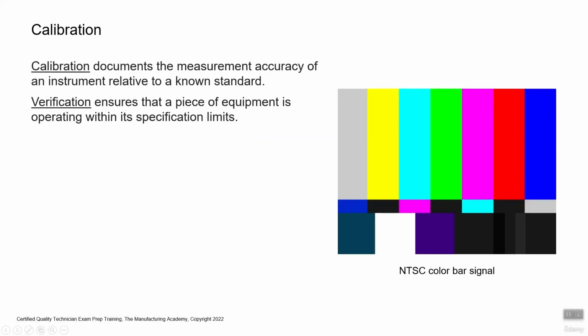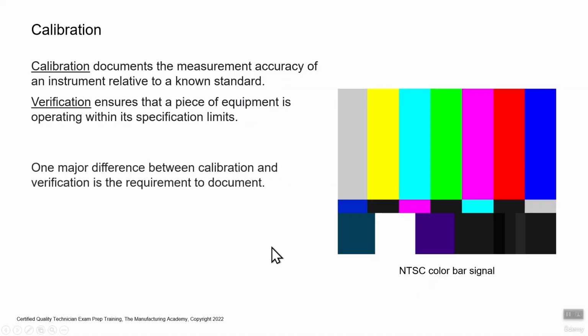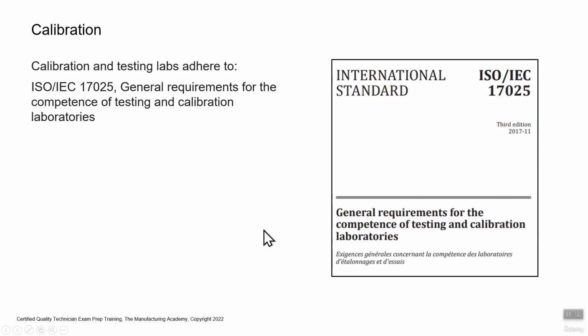So we talked about calibration verification ensures that a piece of equipment is operating within its specification limits. That's sort of like what we were talking before about the micrometers, and you have a gauge block at your workstation, and perhaps at the start of the shift, you're just checking the gauge block to see that your micrometers are reading correctly. One of the major differences, I think you're already starting to see this, between calibration and verification is the requirement to document.